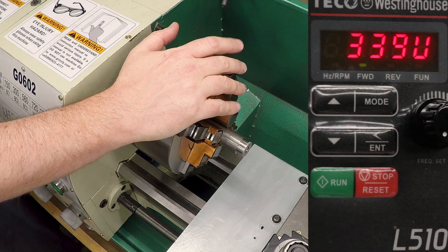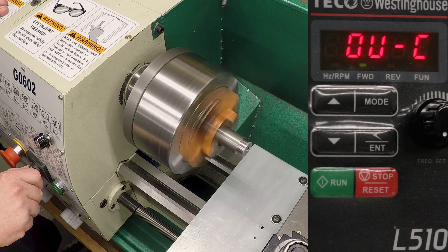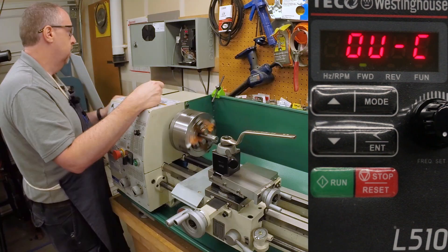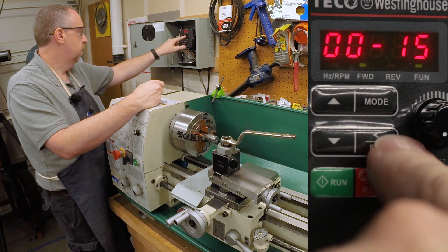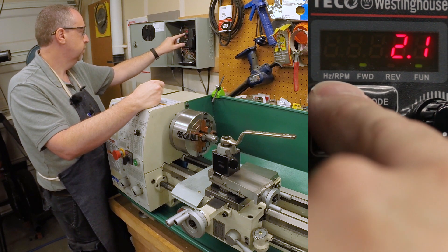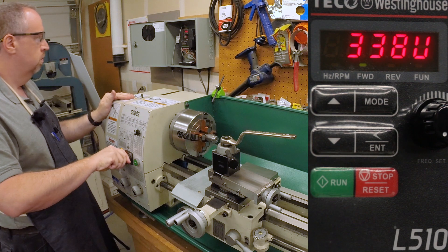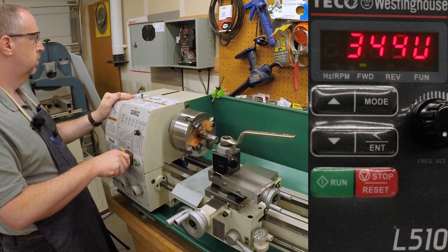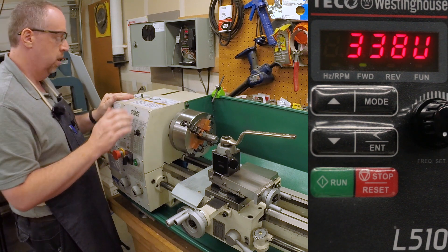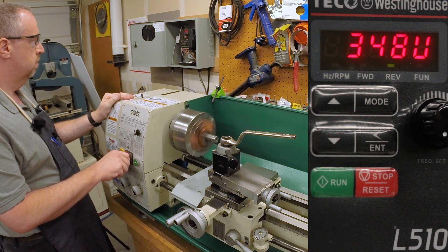Let me reset and watch again, just to see how close that really is. Yeah, it's definitely hitting that 380 pretty quick. So let's lengthen this out slightly — another half second. That seems to work; that gets us up there and still gets it stopped in two and a half seconds. Try reverse — I can live with that.